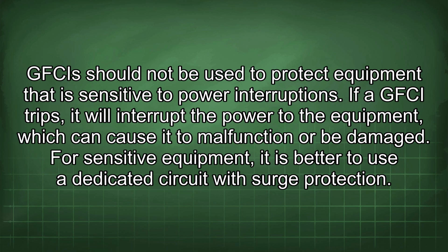GFCIs should not be used to protect equipment that is sensitive to power interruptions. If a GFCI trips, it will interrupt the power to the equipment, which can cause it to malfunction or be damaged. For sensitive equipment, it is better to use a dedicated circuit with surge protection.